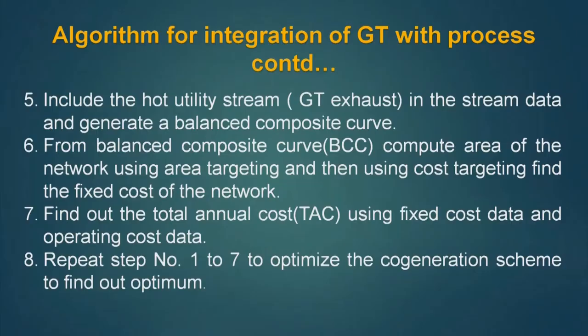Find out the total annual cost using fixed cost data and operating cost data. Operating cost will obviously be the cost of hot utility and cold utility, and we can also use the pressure drop data. Repeat steps 1 to 7 to optimize the cogeneration scheme. We can have different cogeneration schemes with different temperatures of the exit gas, and for all those techniques we have to find out the TAC value to find out the optimum.